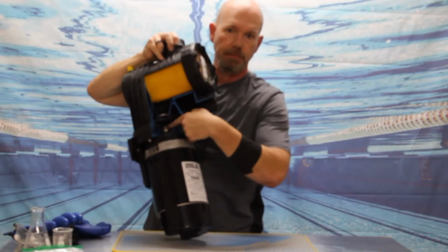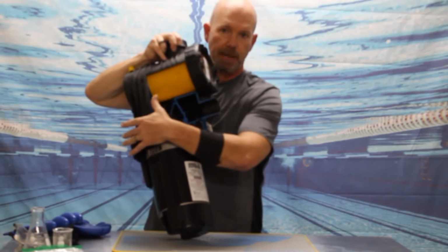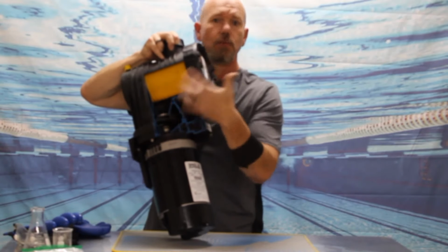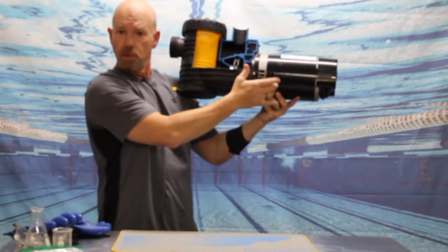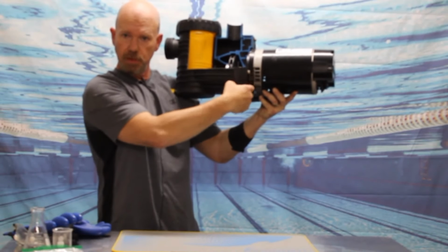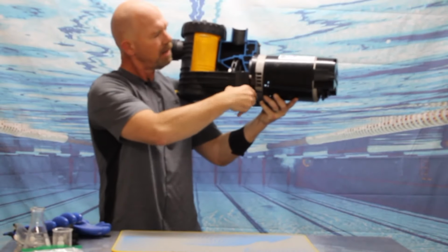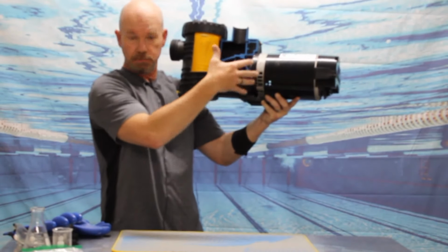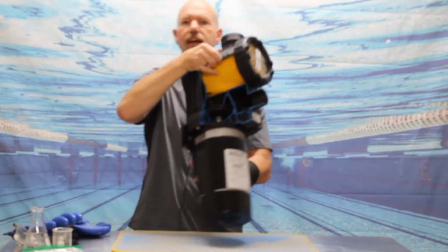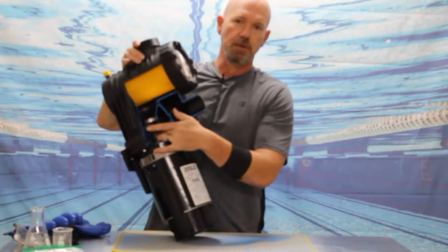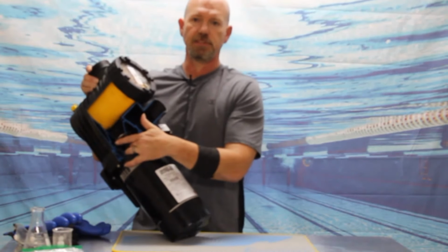The whole purpose of the pump seal is to let the shaft of the motor into the wet end without allowing the water to drip out. So that makes it easy for us to check. With the pump running, take a look beneath where the motor mounts to the wet end. What we're looking for is moisture or any dripping down in this area. If you see any puddling down there, or sometimes you can actually just see a drip, then we know that the pump seal has failed, and the solution would be to replace the pump seal. And again, that's the furthest point back in the system that we can have a suction side leak.